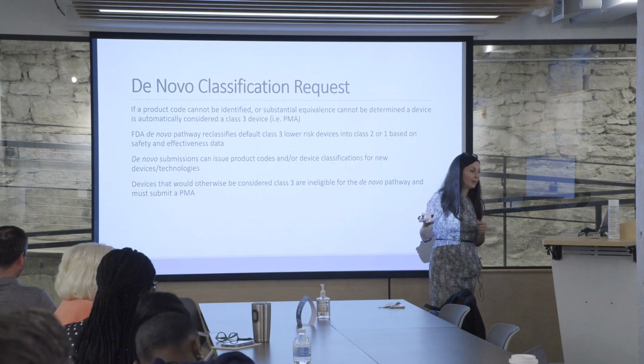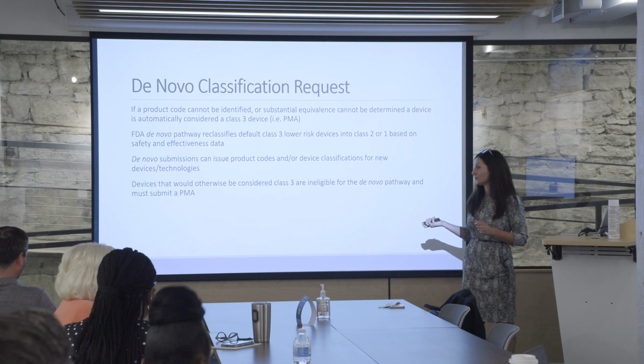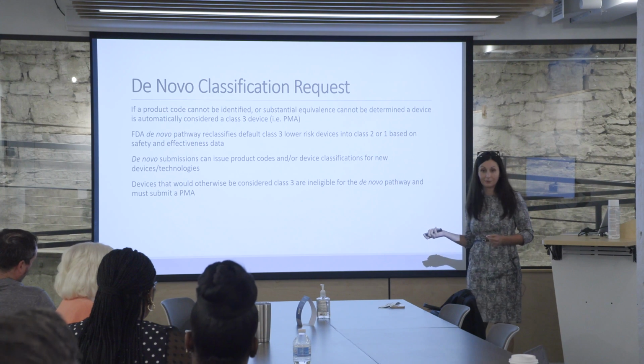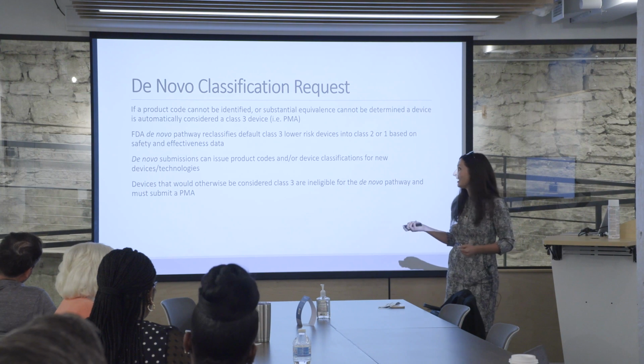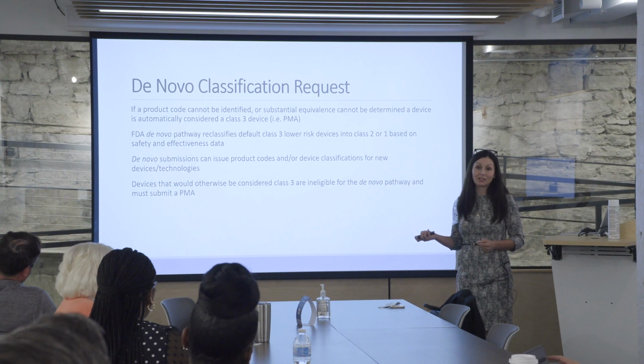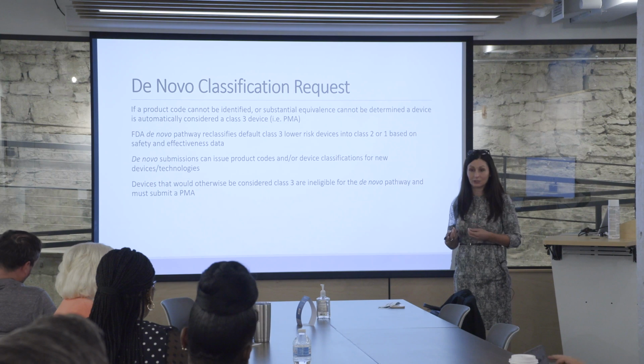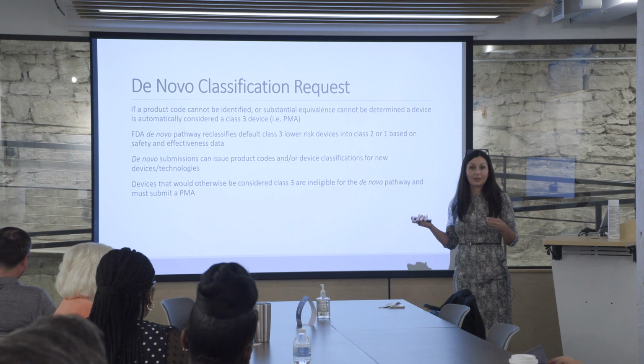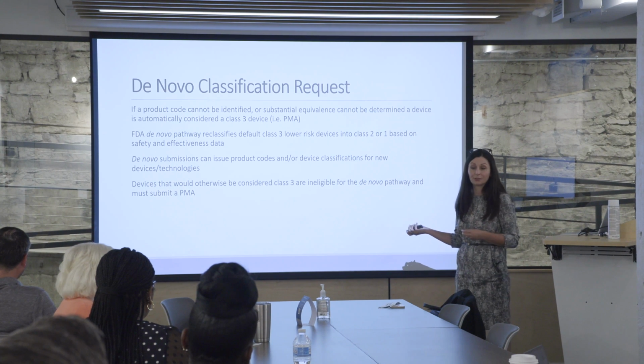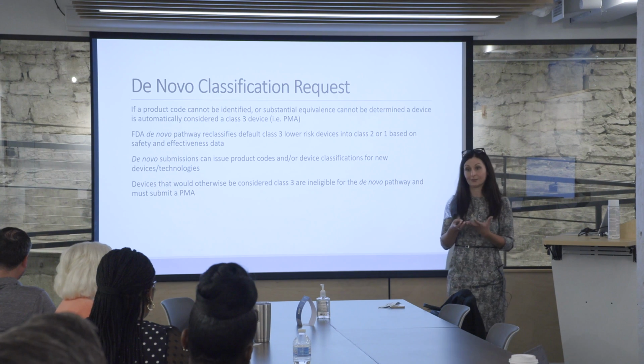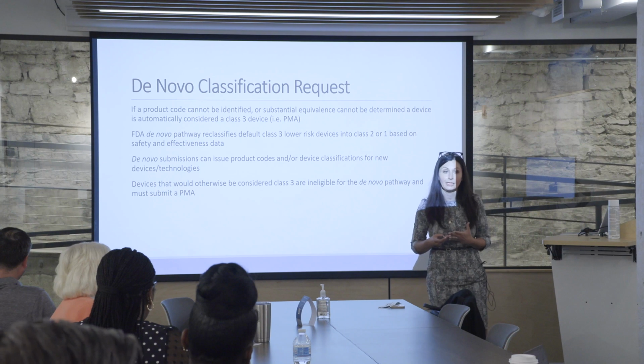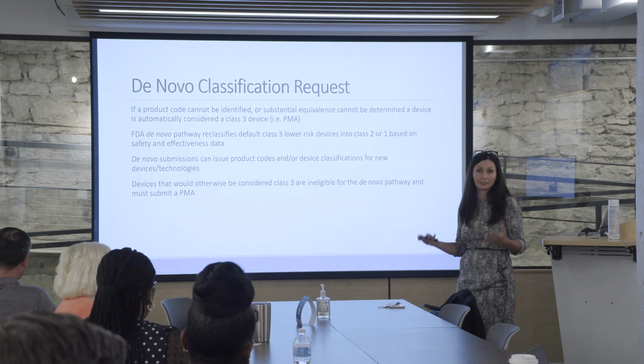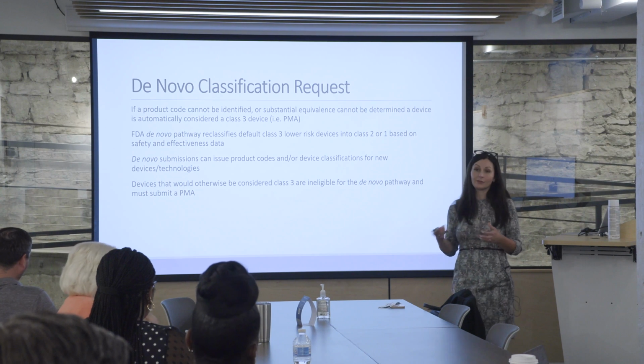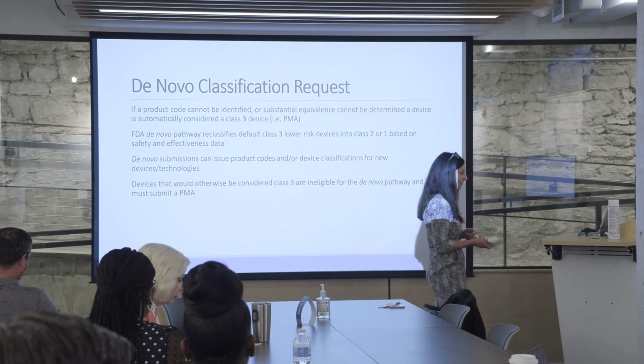We talked a little bit about de novos. So again, the De Novo request is a reclassification request. If you have a product that you can't find a predicate for, which does happen, but it is low risk, you can pursue the De Novo pathway. And again, that has a lot of the same content as a 510(k), but it also has information about what special controls are needed for FDA to assure safety and effectiveness going forward if they make that reclassification for your product.